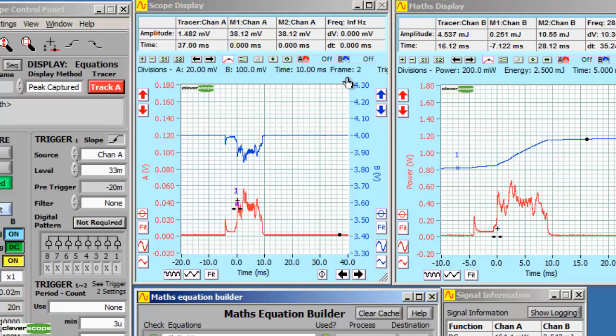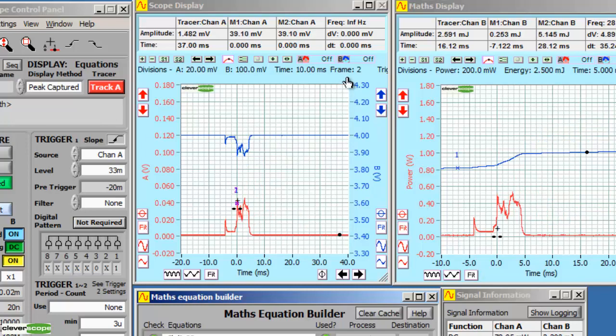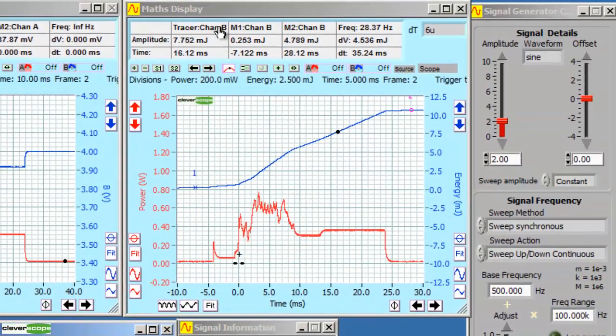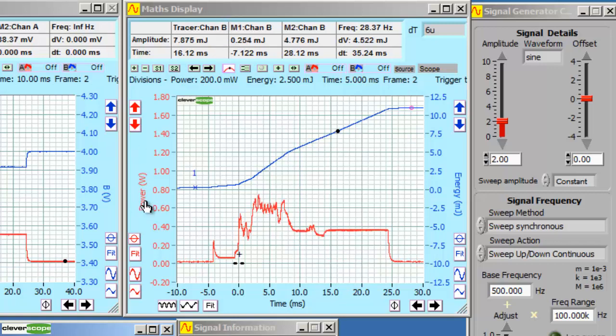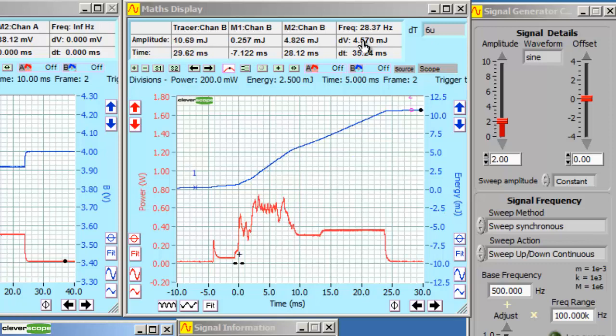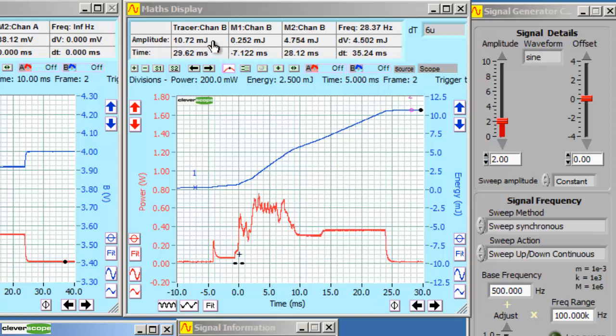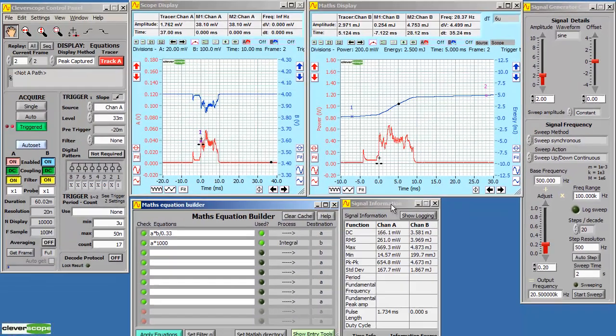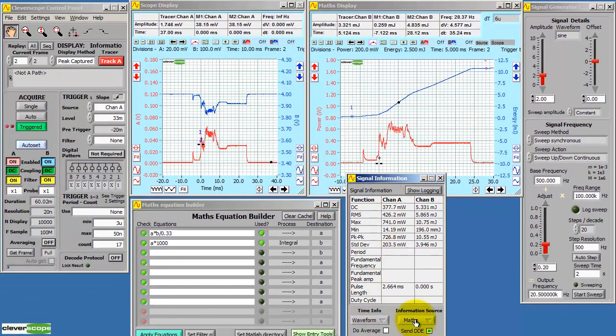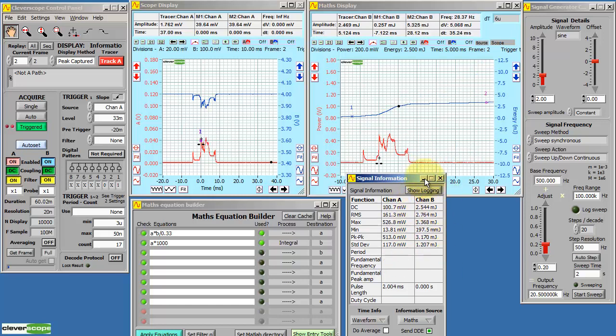Cleverscope includes the ability to scale and name all of the analog values. In this situation, we've used the maths display to display power and energy. In the correct units, watts and millijoules. Up here, in the marker and tracer positions, we see values that are displayed also. In millijoules and watts. And in the signal information, we've set the source to maths. So we also get the correct units, watts and joules.